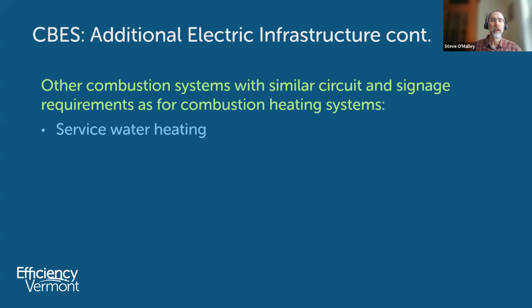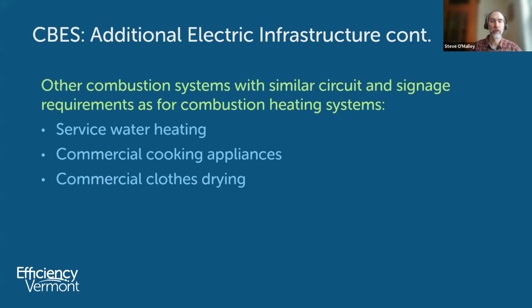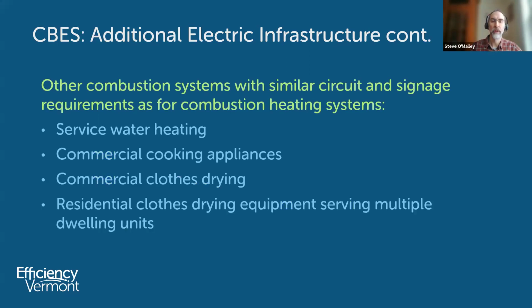There also need to be similar circuit and signage requirements for other combustion systems, such as service water heating. If you have a propane or natural gas fired direct domestic hot water system, you need to future-proof for electrification. The same applies to commercial cooking appliances, commercial clothes drying, and residential clothes drying equipment serving multiple dwelling units—like when you have natural gas dryers.